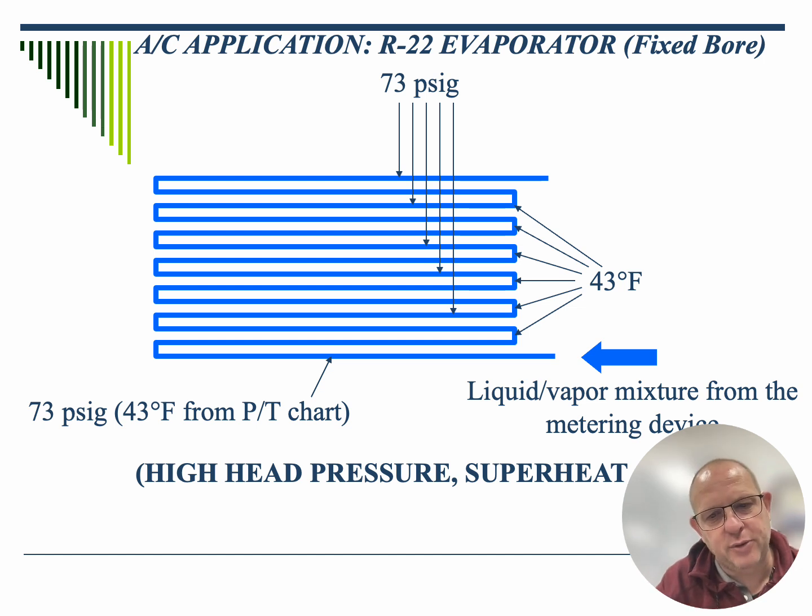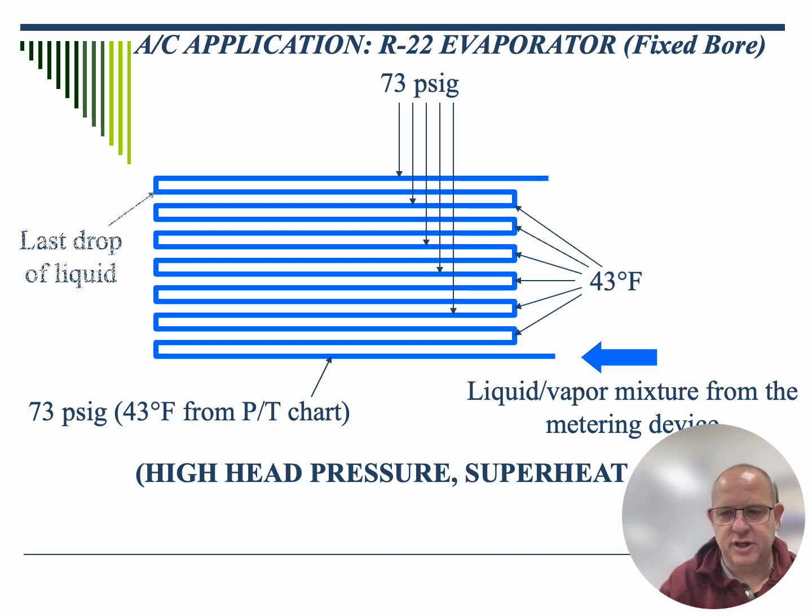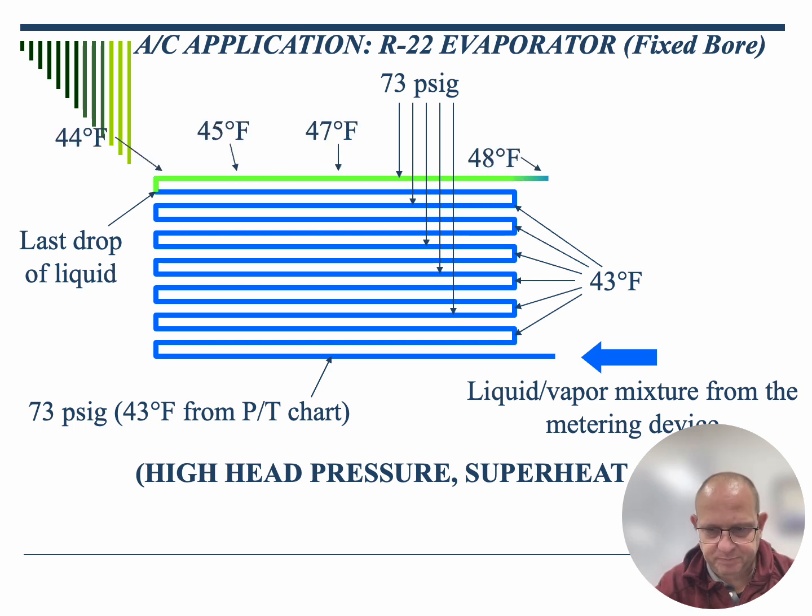The same principle goes into the amount of refrigerant flow in the evaporator as the temperature outside increases as well. So you are going to end up with more refrigerant inside of the evaporator if the pressure behind the orifice is pushing more of that refrigerant into the system itself. So in this condition, we have a system with a high head pressure. The increase in head pressure has increased the flow of the refrigerant through that device itself.